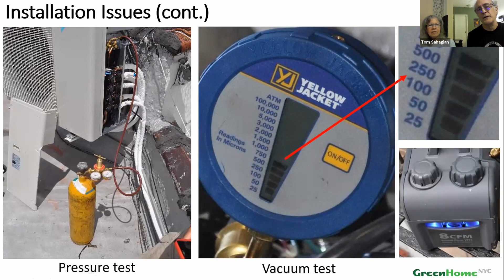So once we were able to get the proper gauges for the pressure test, this was a bit of a challenge, because what happens is if you start off and the pressure is at 550 or a little bit over, which is what the manufacturer recommends, and then they recommend a certain number of hours that it needs to hold that pressure.